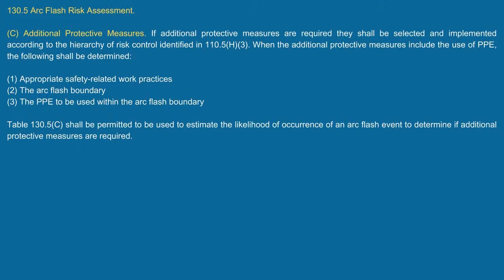Maybe I have a non-conductive rope in there. If something happens, I have it tied around his waist. If an arc does occur and knocks him back, I can grab that rope. I'm outside the arc flash boundary, the limited approach boundary, all that, and I can pull him out of there. You see what I'm saying? Yeah, and that's part of your rescue plan with OSHA too. You have to comply with OSHA as far as electrical safety, and you have to have a rescue plan.